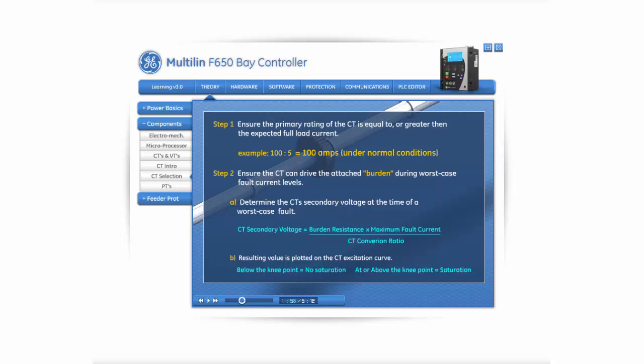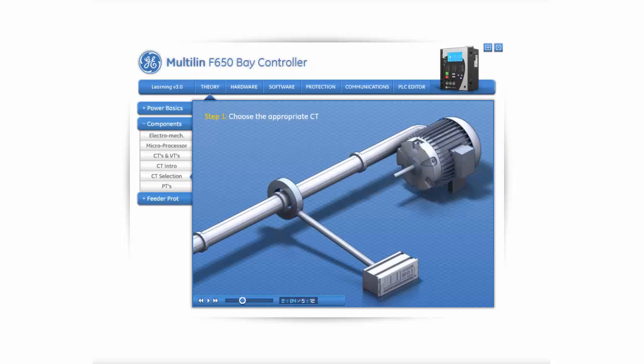Now we will look at a practical example to help us further explain this calculation. Let's assume that we have a motor that draws a maximum full load current of 285 amps. The first step is to choose the appropriate CT. It is customary to select a CT that has a primary rating falling between 50 to 100% of our maximum full load current, in this case 285 amps. Possible CTs for this use would be 300 to 5, 400 to 5, and 500 to 5 CTs, because the primary rating falls between 50 to 100%. In this case, we would select the CT that would fall the closest to 100%.